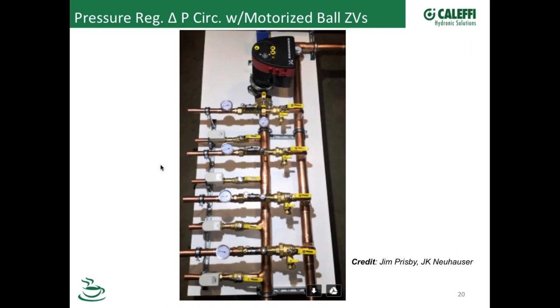That was one of Cody's creations there, that we had that call come in and Cody said, well, let's just get a little RIB relay or something like that. That's a double throw relay. And so I think you put a little graphic together, a little schematic of how to wire that, so that if you do put one of these valves in and say, wait a second, I can't get the valve to close, Cody came up with a fix and a little schematic of how you can put a RIB relay into our relay box and have that ability for that valve to get power to open and also power to close with a standard thermostat, without having to go to a three-wire thermostat that powers both ways.